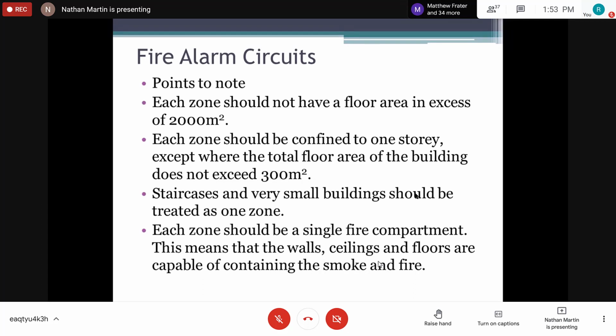Each zone should be a single fire compartment. This means that the walls, ceiling, and floors are capable of containing the smoke and fire. It means that if you are putting in a ceiling and there's a wall that separates them, the wall must continue to the roof of the building. It can't stop halfway in the building, right? You have to continue to the top of the building.